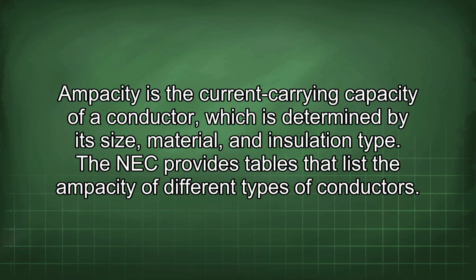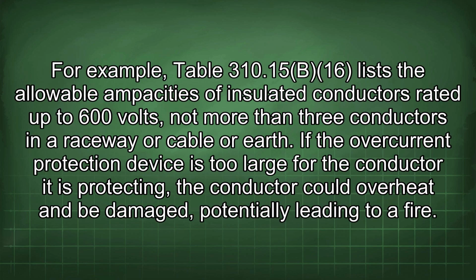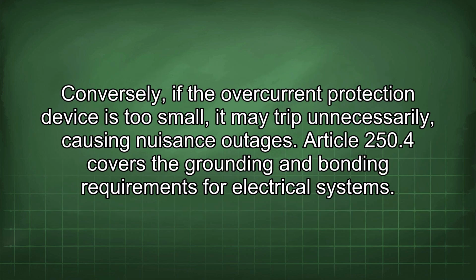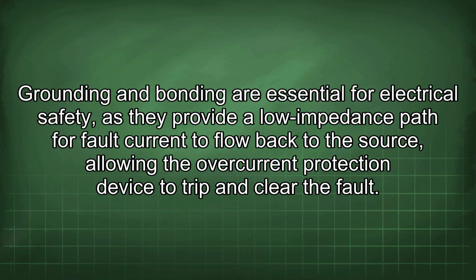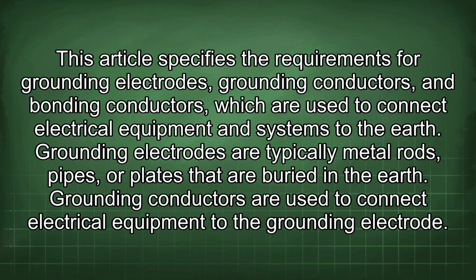The NEC provides tables that list the ampacity of different types of conductors. For example, Table 310.15(B)(16) lists the allowable ampacities of insulated conductors rated up to 600 volts, not more than 3 conductors in a raceway or cable or earth. If the overcurrent protection device is too large for the conductor it is protecting, the conductor could overheat and be damaged, potentially leading to a fire. Conversely, if the overcurrent protection device is too small, it may trip unnecessarily, causing nuisance outages. Article 250.4 covers the grounding and bonding requirements for electrical systems. Grounding and bonding are essential for electrical safety, as they provide a low impedance path for fault current to flow back to the source, allowing the overcurrent protection device to trip and clear the fault. This article specifies the requirements for grounding electrodes, grounding conductors, and bonding conductors, which are used to connect electrical equipment and systems to the earth.